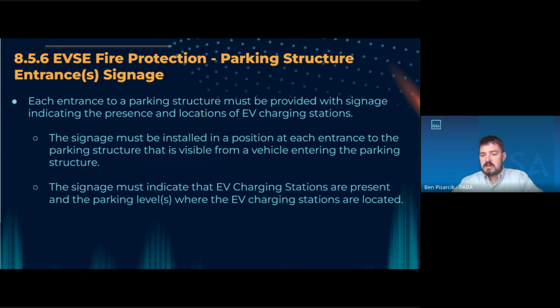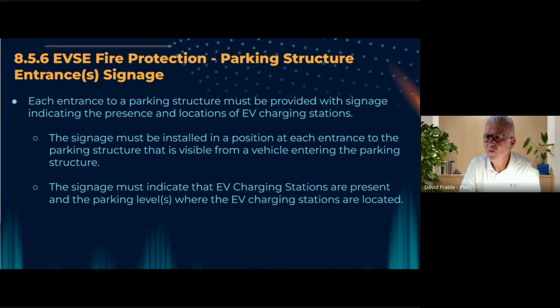Okay. Any other questions out there? Oh, see one just came in. What about shunt trip? We do not have a requirement for shunt trip with activation of the sprinkler system. Is there a concern? We got manual power disconnecting means installed within the facility.